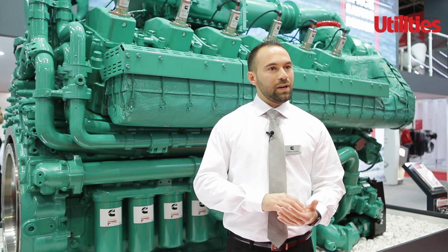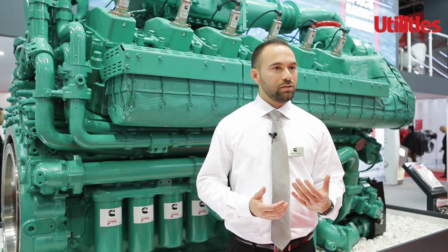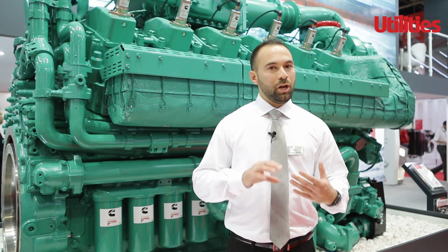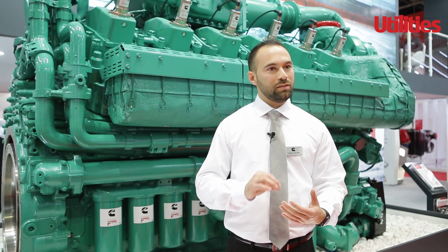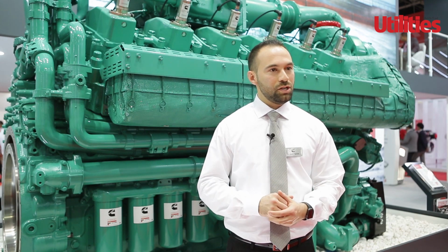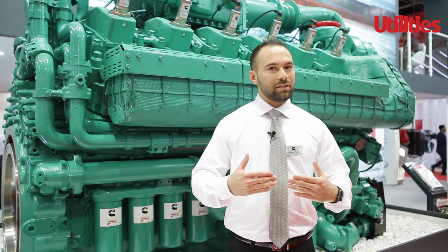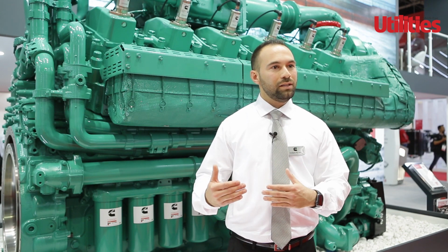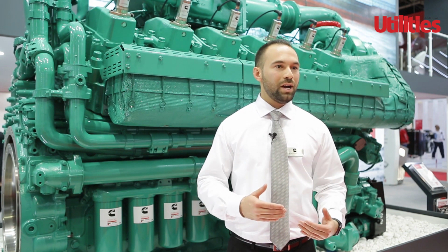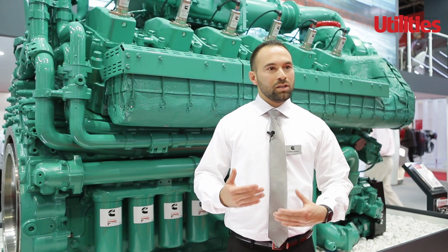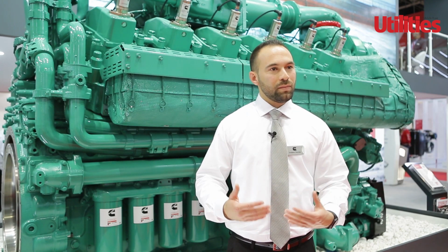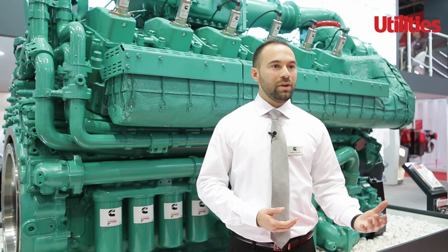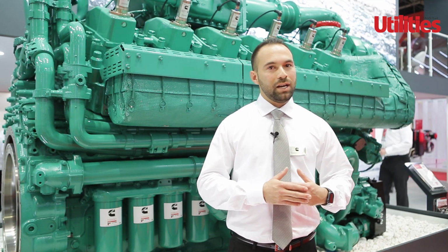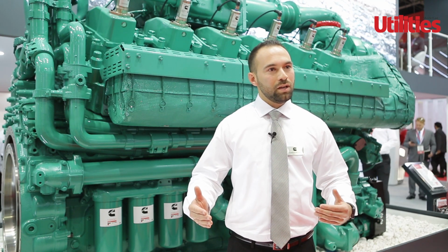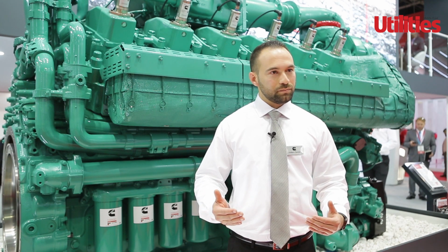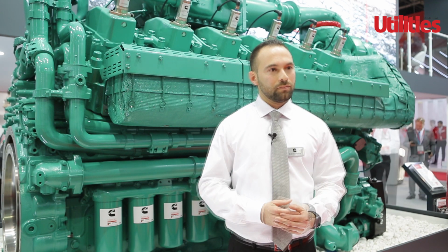We also have a built-in methane sensor and NOx sensor. The NOx sensor helps us ensure we meet the desired emissions of the engine and keep that standard all the time, so a service engineer has less time needing to come back and readjust the engine. That's why we call it a self-calibrating, self-adjusting engine. Especially with the methane sensor, that helps us have wider flexibility on gas acceptability and even fuel variation.